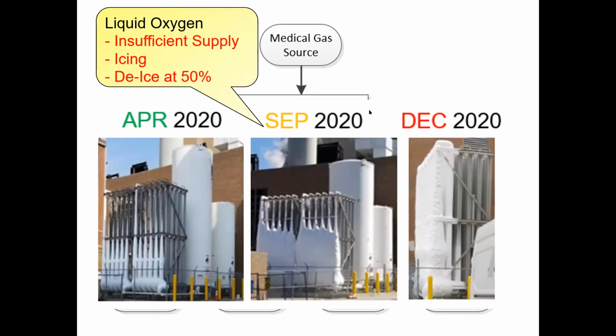And so there are three things to be concerned with here. Insufficient supply should not be a problem if you know what your usage is, because you're going to have tanker cars coming up and supplying these all the time. More of a problem might be icing. As you can see here, this is from our own institution. Just over the course of the year, you can see that the icing has gotten much worse as the peak demand has gone up. And we have decided to act and to de-ice these heat exchangers if they reach 50%. And here you can see one is already at 30%.